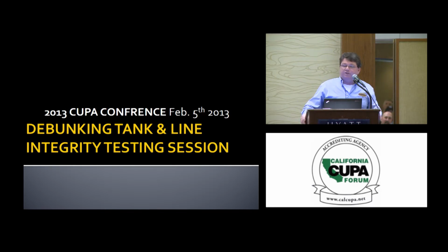So I have about 4 or 5 places. My boys, Diamond Shamrock, I don't think I got anybody in here, but Texas. There's been a couple times where in clay, they wanted an overfill test. There's a couple situations where it's needed to be done, on the coast with tidals, things like that. You had to have some situations that were adjustable to water table. The science of testing, it still hasn't left us, I believe.